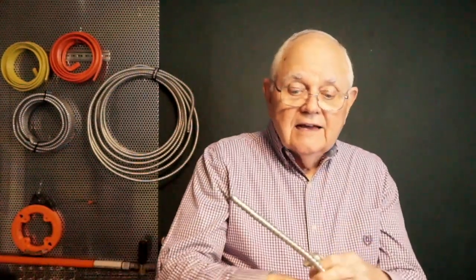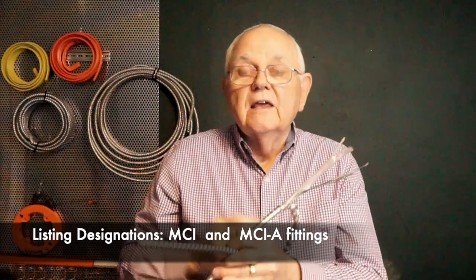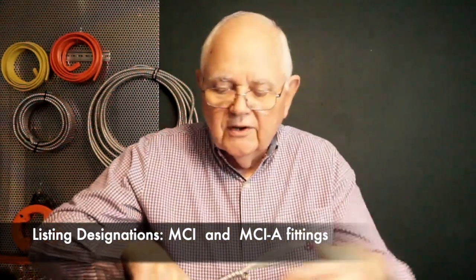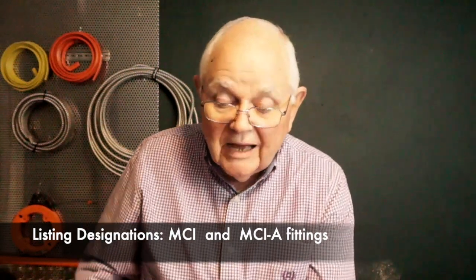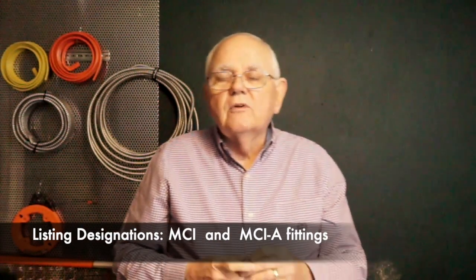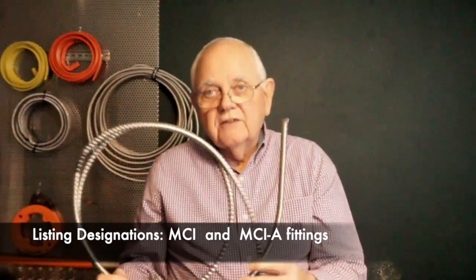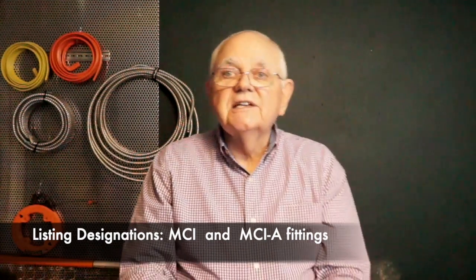What is that all about? Okay, so the MCI would just simply be metal-clad cable. Then the MCI-A tells me that it's the metal-clad cable, and it would have the aluminum conductor coming out that I could then put my fitting on, and that would give me bonding for my equipment grounding conductor. So if that's what I'm going to be doing, using that additional equipment bonding conductor, I call it, inside the MC cable, where it makes contact with the entire run of the MC cable, then my fitting has to be listed as MCI-A. So different types of fittings, whatever you need, you can buy it.